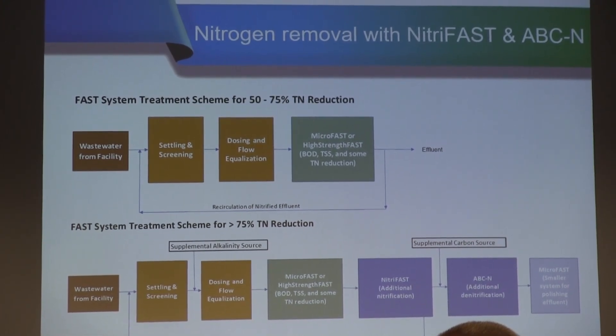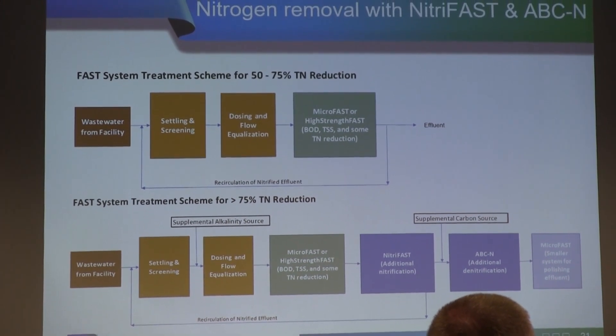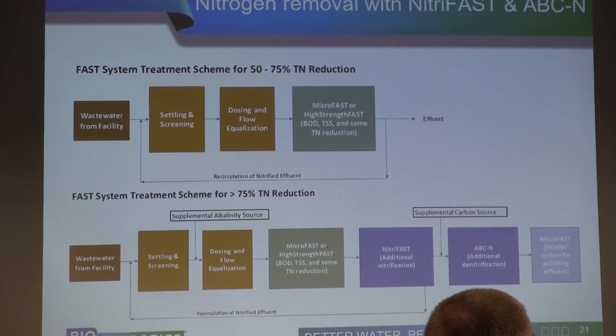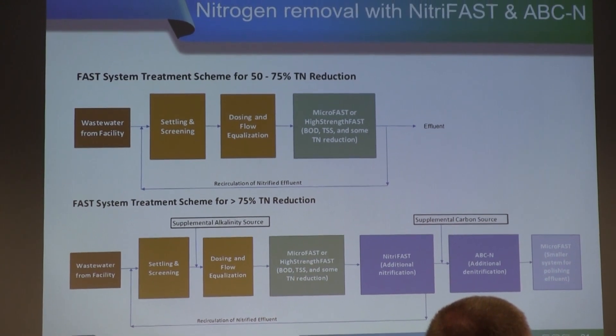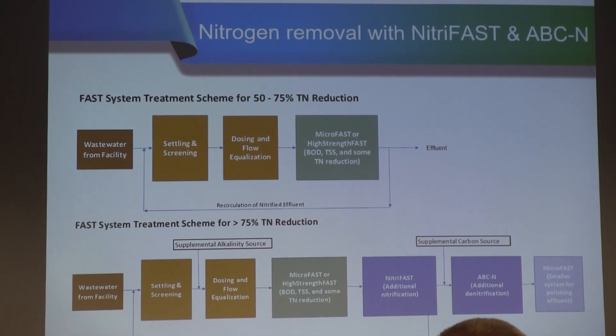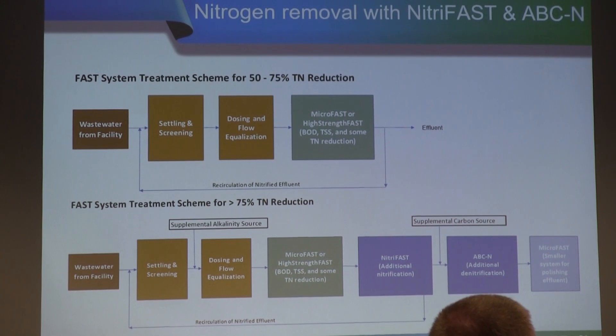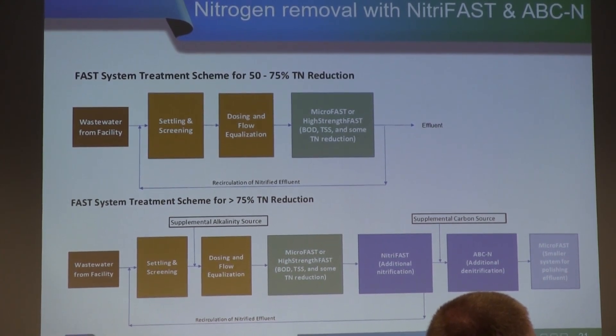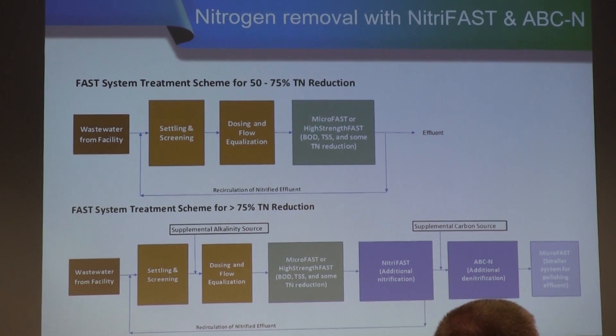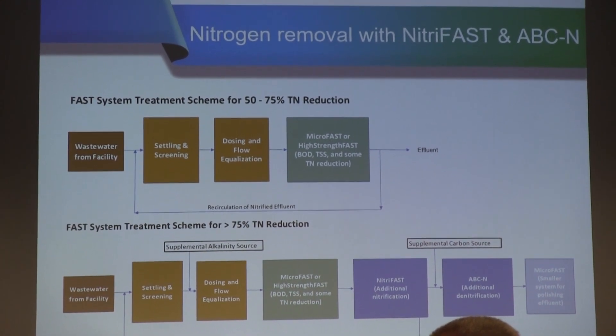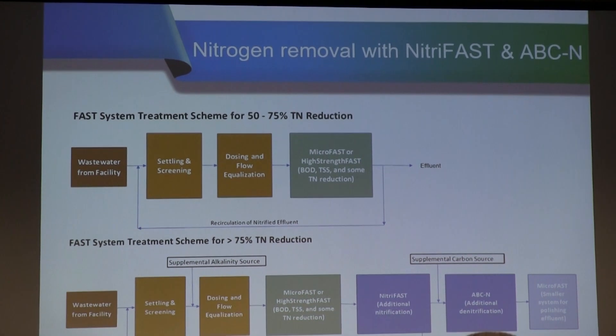To maximize nitrogen removal, you have to keep the chemistry of the wastewater in balance. Alkalinity is supplied primarily by baking soda, or sometimes a stronger base like sodium hydroxide, though baking soda is safer to handle. On the denitrification side, a limiting factor is often a carbon source — essentially BOD. When the balance of BOD and total nitrogen isn't where it needs to be, you add a carbon source such as Micro C, which provides organic carbon for denitrifying bacteria. Plan to include chemical feed lines for adding these chemicals if targeting a very low total nitrogen limit.